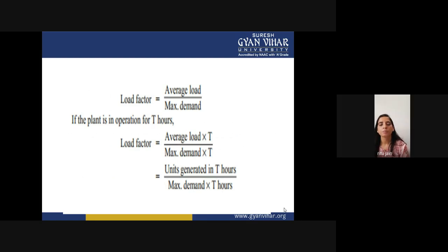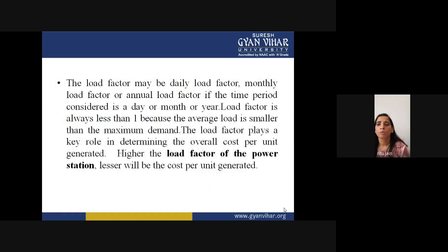If you want to calculate the average load of this, suppose you are using 100 watt for 1 hour, 200 watt for the next 3 hours, then you will calculate the average load. When you divide this average load by maximum demand, suppose 200 watt, then the load factor is always less than 1. So the average load is always smaller than your maximum.